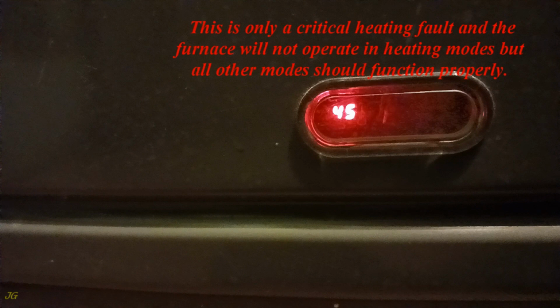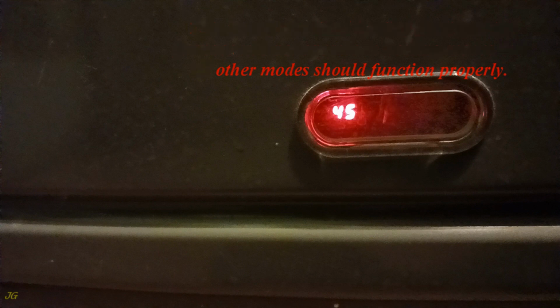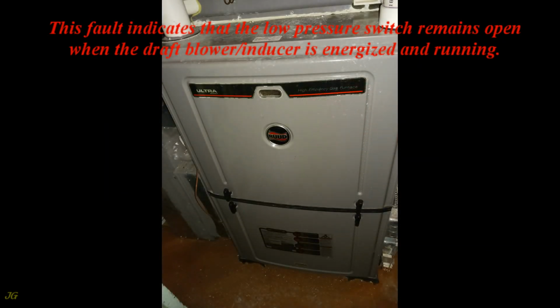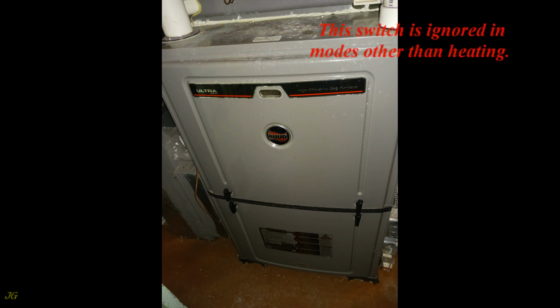This is only a critical heating fault and the furnace will not operate in heating modes, but all other modes should function properly. What is error, fault code 45? This fault indicates that the low pressure switch remains open when the draft blower inducer is energized and running. This switch is ignored in modes other than heating.